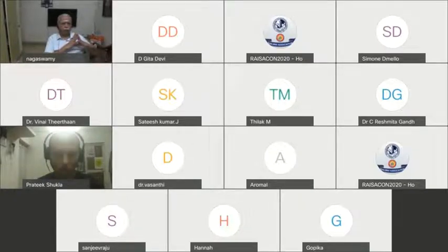Second thing is the ground fault circuit interrupter, GFCI. This is a device which monitors the current in the hot and the neutral side of the circuit, and if there is any difference detected, it is assumed that there is current leakage outside the circuit, and thus the power is immediately interrupted. Third thing is the isolation transformer.